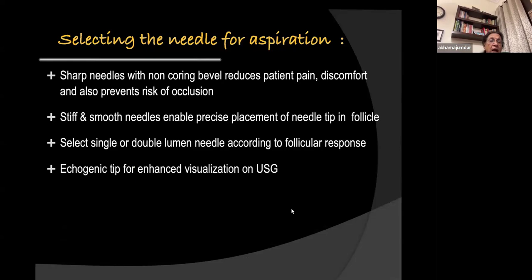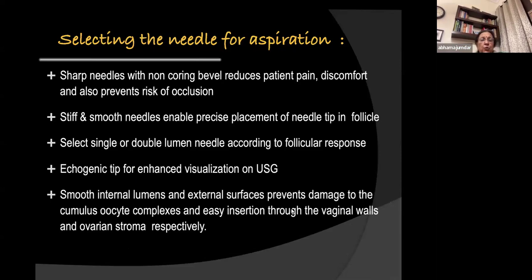All the tips now have an echogenic tip for enhanced visualization on ultrasound. Smooth internal lumens are very important, and therefore we use these needles only once, because once you use them, blood and other debris could collect on the inner surface. If you use them again, they wouldn't have a smooth internal lumen. Even the external surface has to be very smooth so that it pierces through the tissue very easily. Both a smooth lumen and surface prevent damage to the cumulus oocyte complex, and allow easy insertion through the vaginal walls and ovarian stroma respectively.